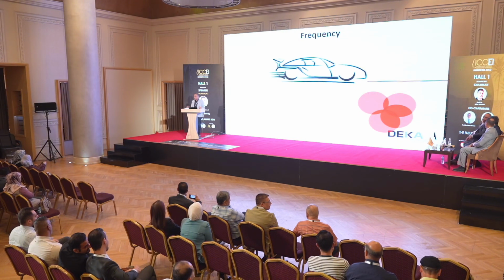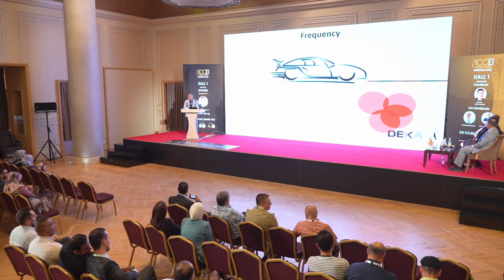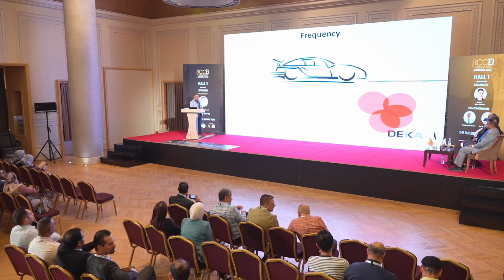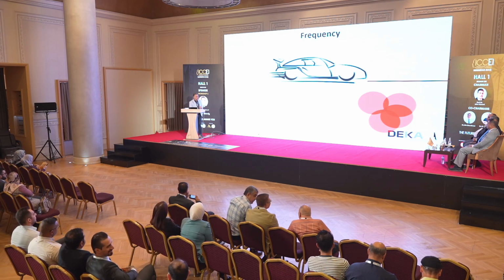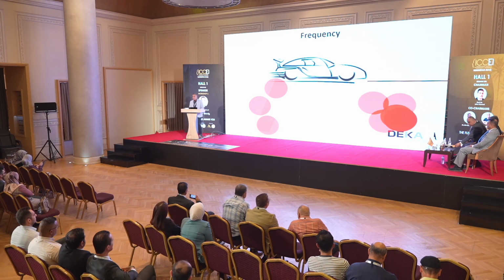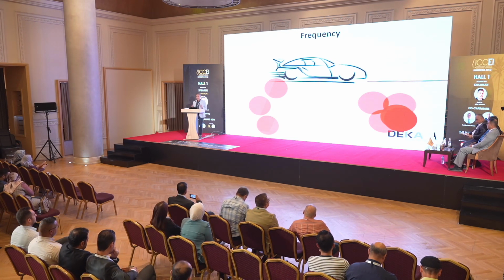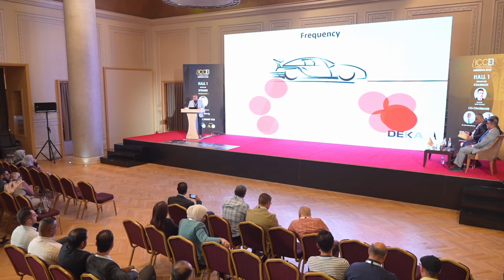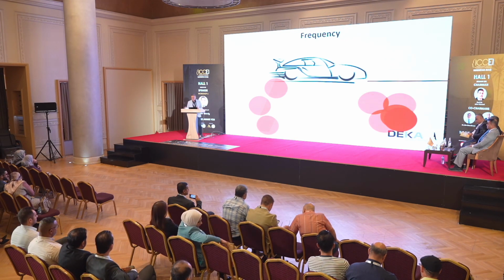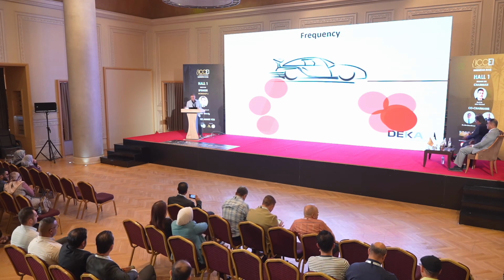So try to avoid overlapping, please, because this could cause burns for the patient, and sometimes in high frequency you can leave many spaces or missed areas. So if you're not professional, please work with low frequency, 1 hertz or 2 hertz, 2 pulses per second, to be sure to avoid stacking or missed areas. You should train enough on high frequency pulses.